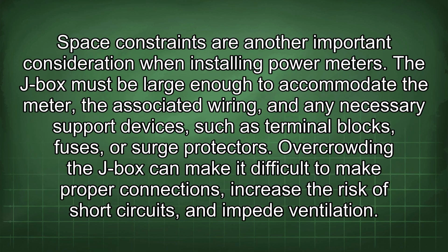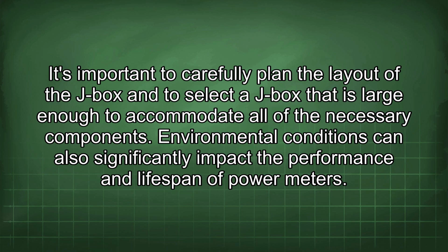Space constraints are another important consideration when installing power meters. The J-box must be large enough to accommodate the meter, the associated wiring, and any necessary support devices such as terminal blocks, fuses, or surge protectors. Overcrowding the J-box can make it difficult to make proper connections, increase the risk of short circuits, and impede ventilation. It's important to carefully plan the layout of the J-box and to select a J-box that is large enough to accommodate all of the necessary components.